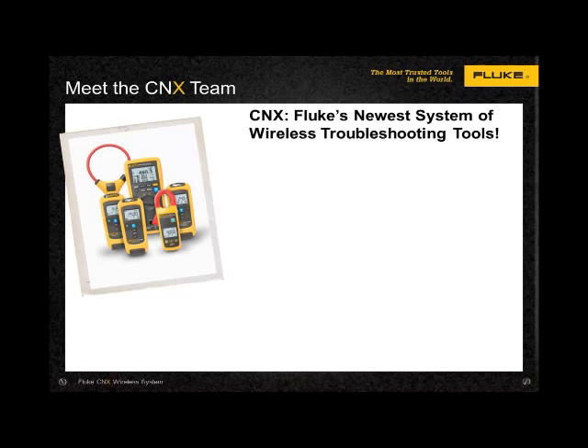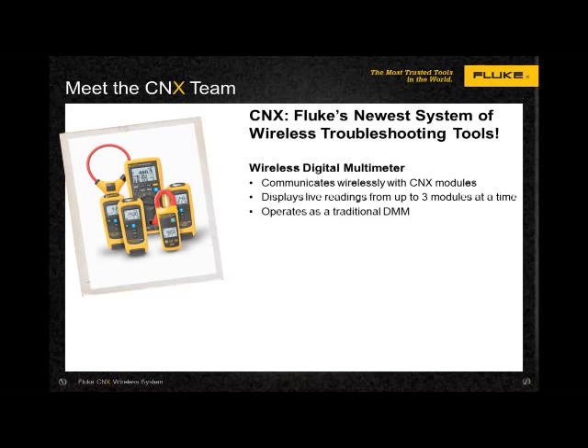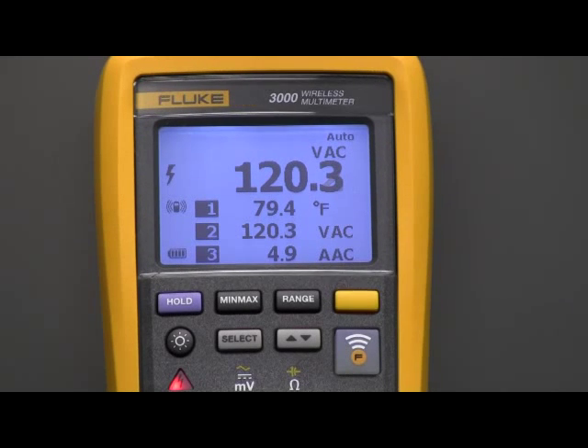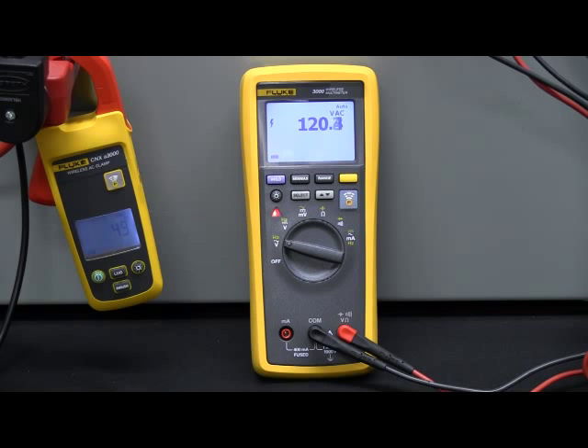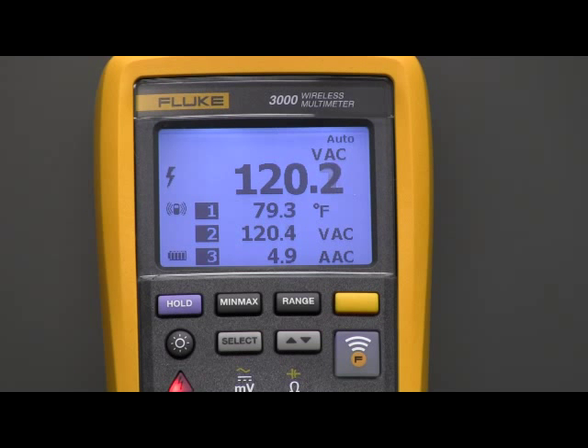Meet the CNX team. At the heart of the system, the wireless digital multimeter is designed to communicate wirelessly up to 60 feet away with CNX modules. The DMM operates as a traditional DMM, even in nasty environments due to its IP ingress protection rating of 54. It will display live readings from up to three modules at a time and can be used as a module itself, sending its readings to a computer or another CNX DMM. The first thing you'll notice is the CNX radio button on the right side of the meter. With a push of the button, the meter will initiate a binding process, discovering available modules and displaying their readings on the display. The display will change slightly when the secure connection is established, now displaying four readings.